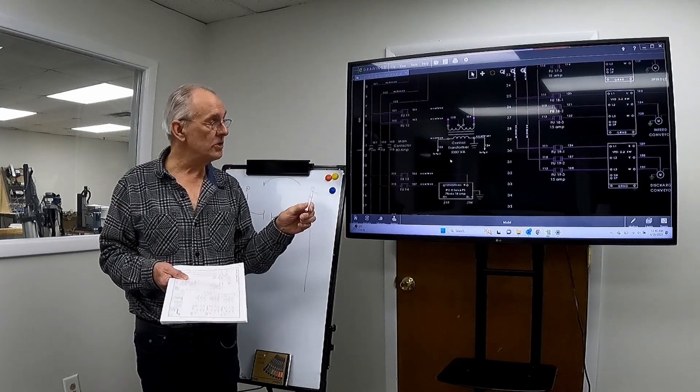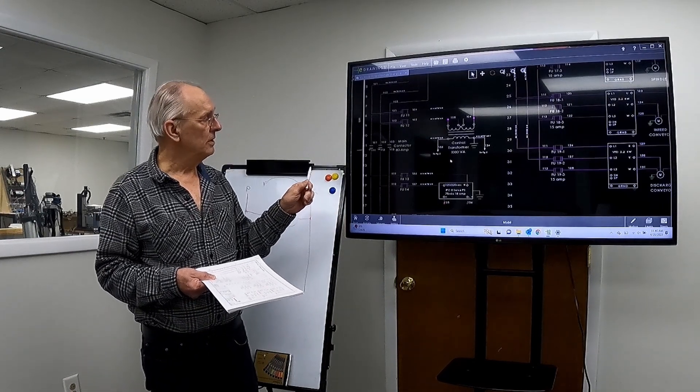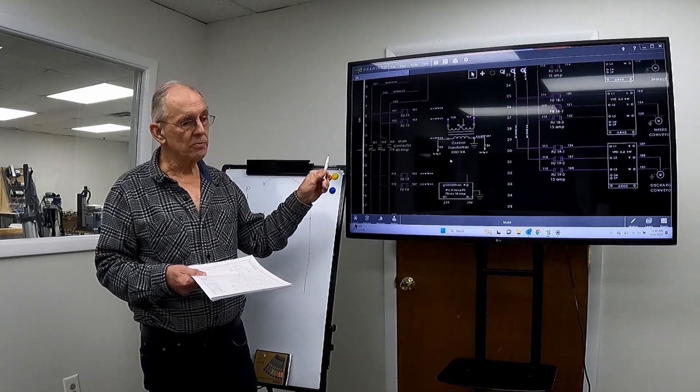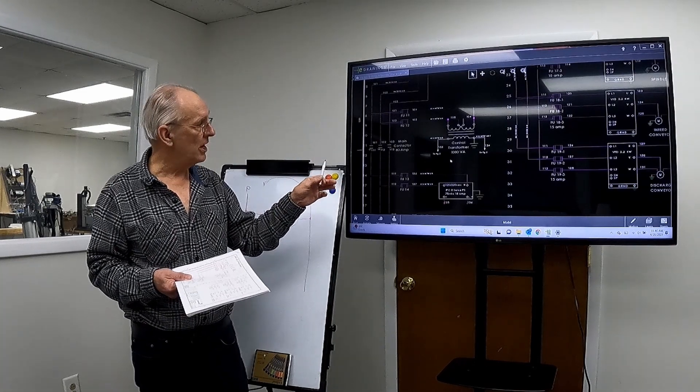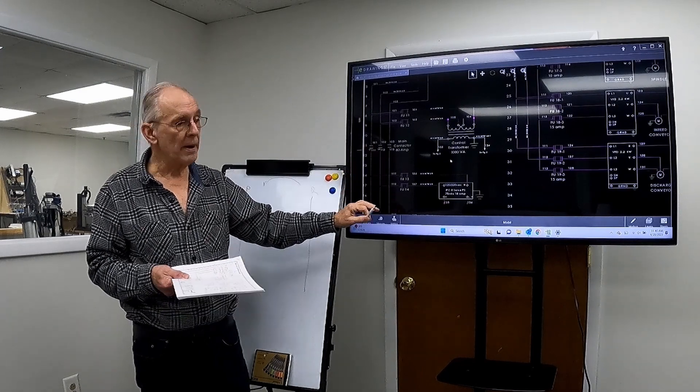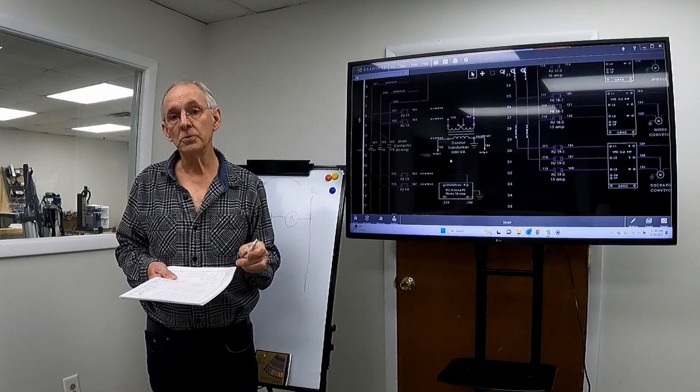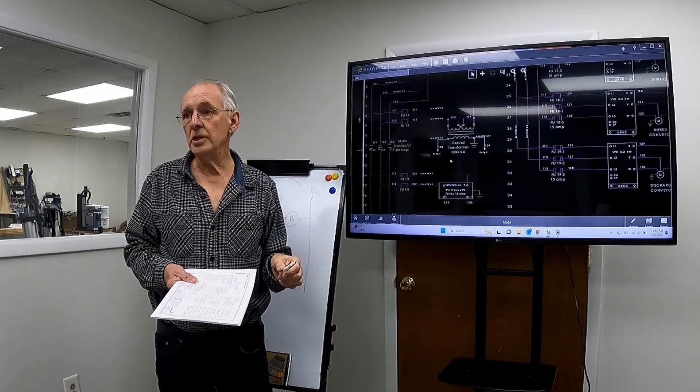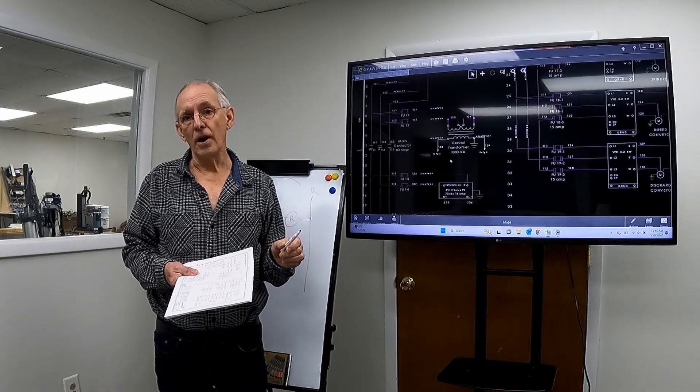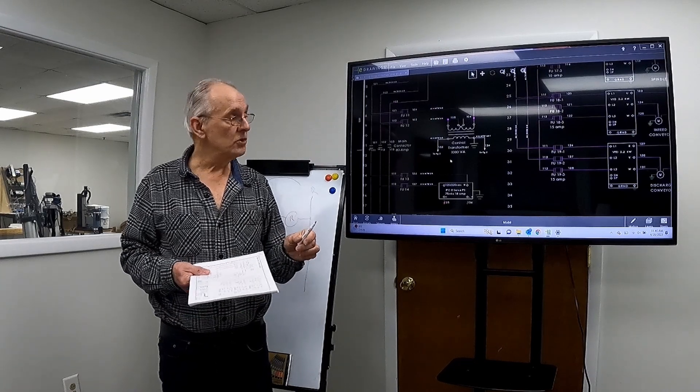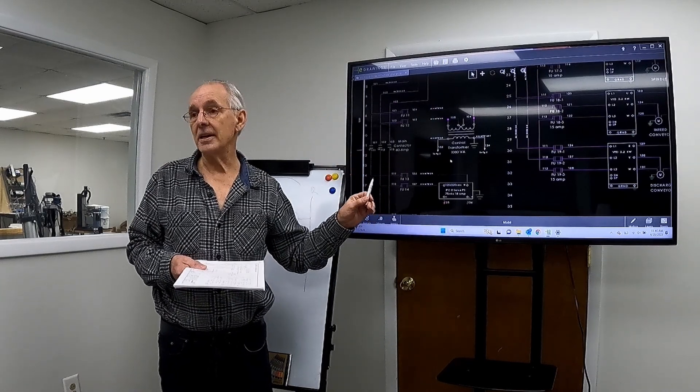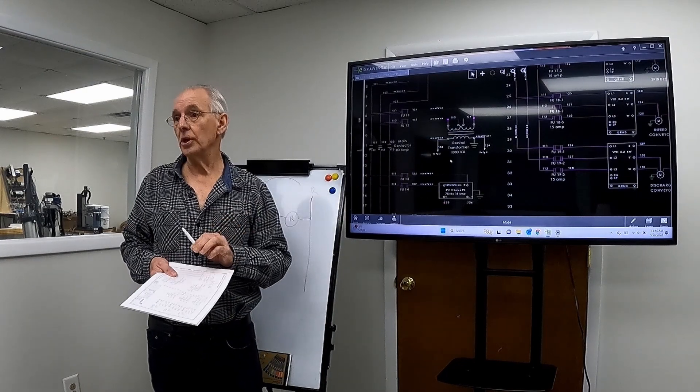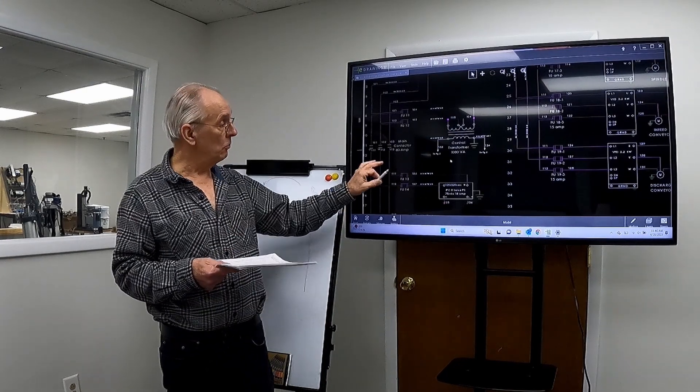And in the case of we break this with the e-stops, and that turns off all the power. But you notice that it doesn't turn off the control transformer. The reason is the machines we build, they need to know where they are and what they're doing, and so the controls stay active even though the main contactor shuts off the power.